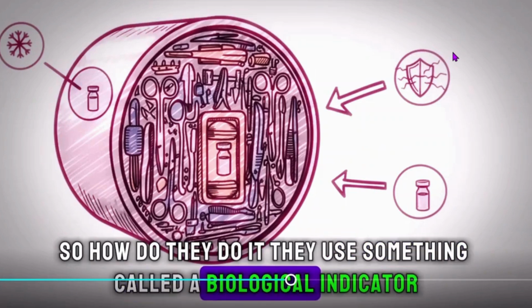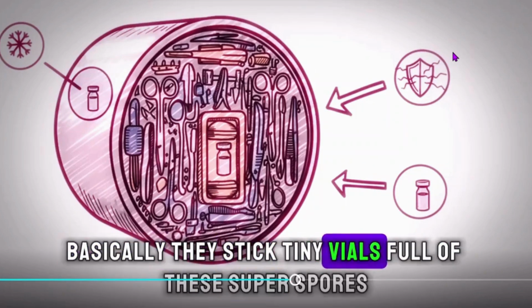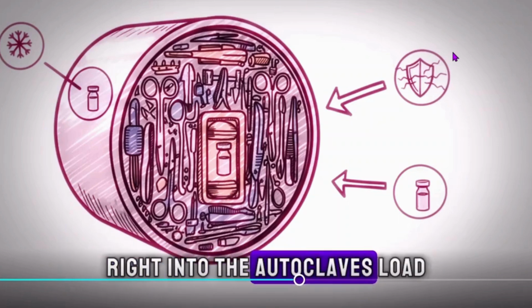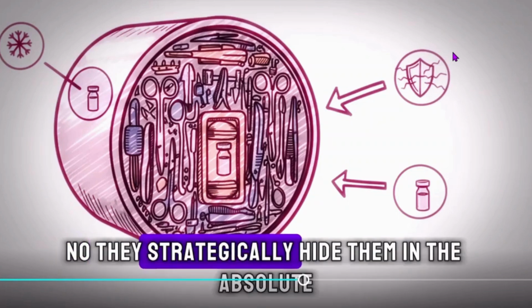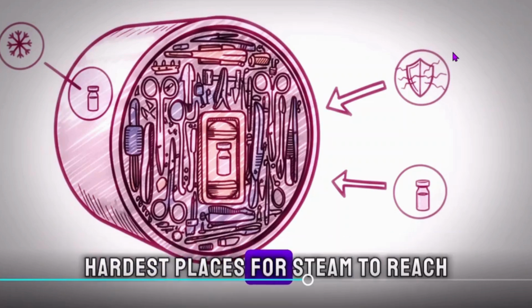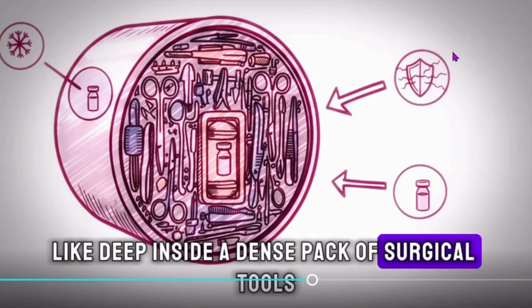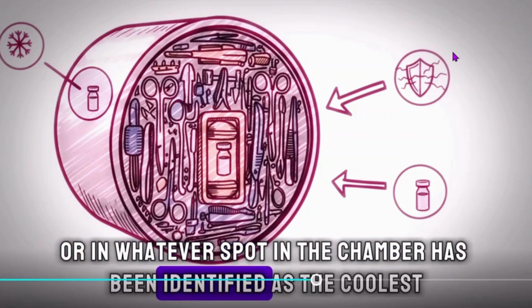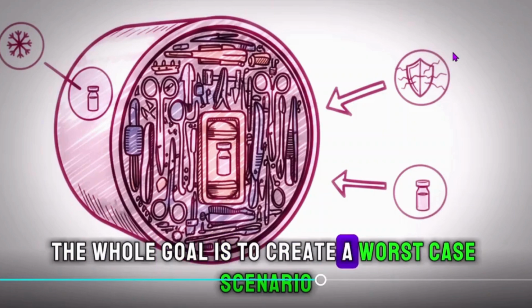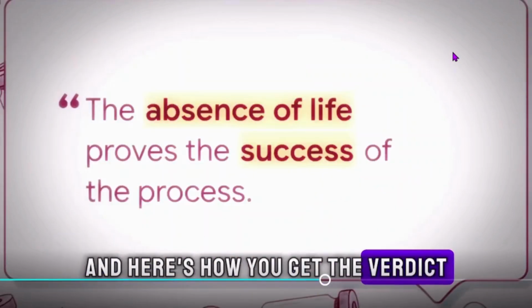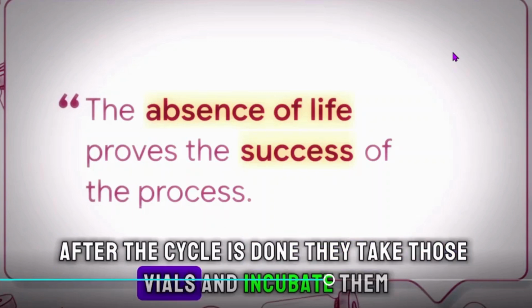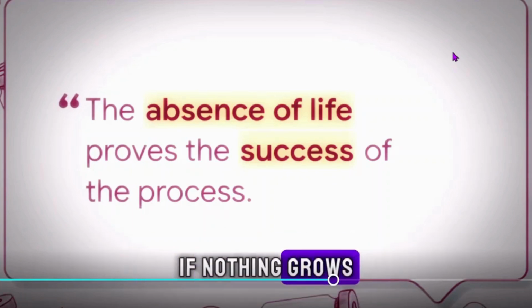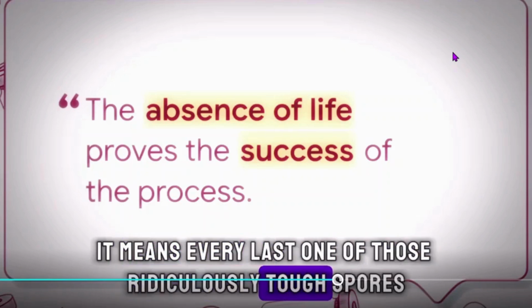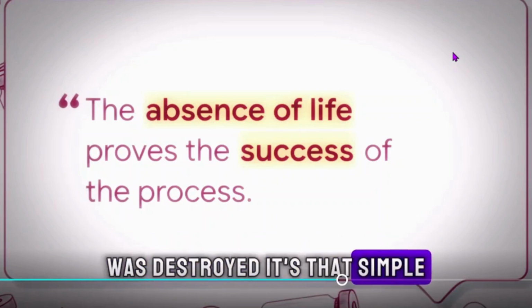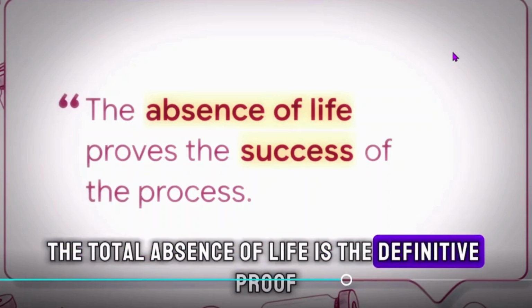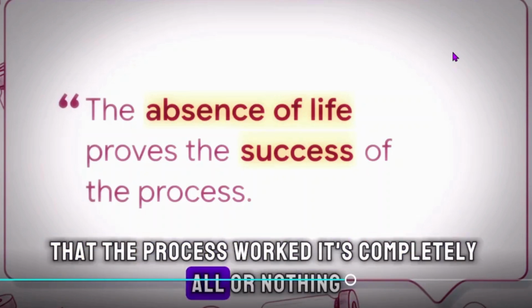So how do they do it? They use something called a biological indicator. Basically, they stick tiny vials full of these superspores right into the autoclave's load. And they do not make it easy. No, they strategically hide them in the absolute hardest places for steam to reach, like deep inside a dense pack of surgical tools or in whatever spot in the chamber has been identified as the coolest. The whole goal is to create a worst-case scenario. And here's how you get the verdict. After the cycle is done, they take those vials and incubate them. If nothing grows, it means every last one of those ridiculously tough spores was destroyed. It's that simple. The total absence of life is the definitive proof that the process worked. It's completely all or nothing.